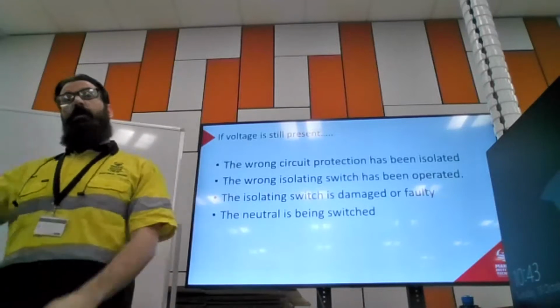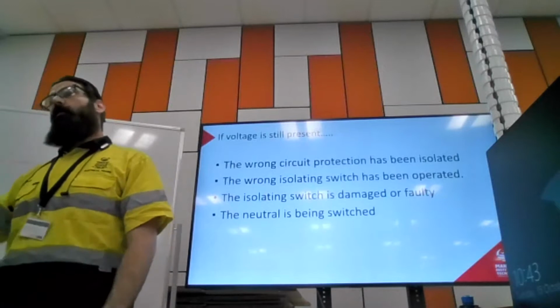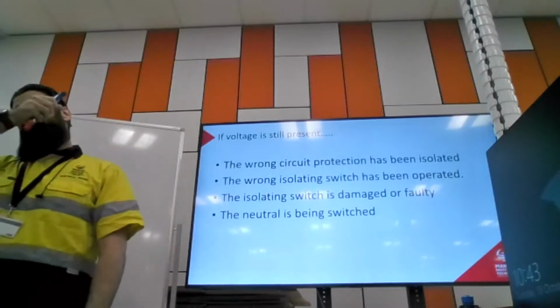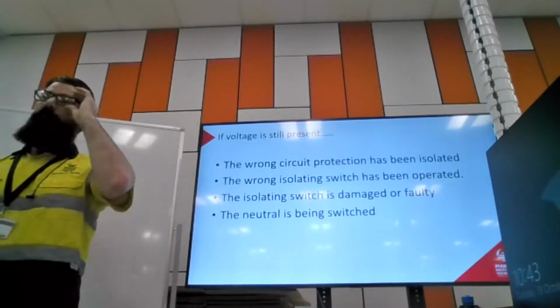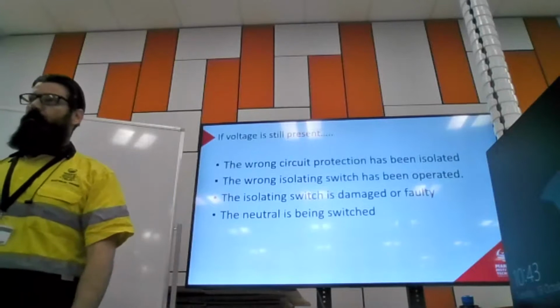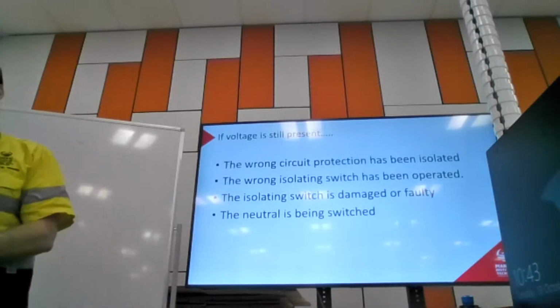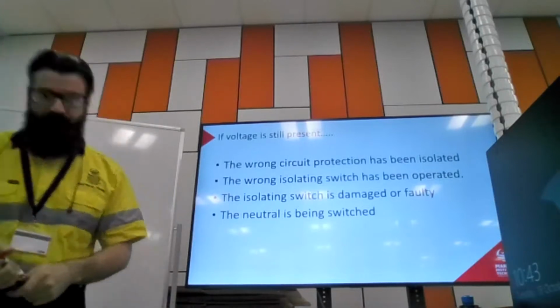And that means that in the equipment they then started working on, or the one that accidentally turned off, when they started investigating, all of the neutrals are live because they switched the neutral back at the switchboard accidentally. So that person ended up getting a shock off a neutral.